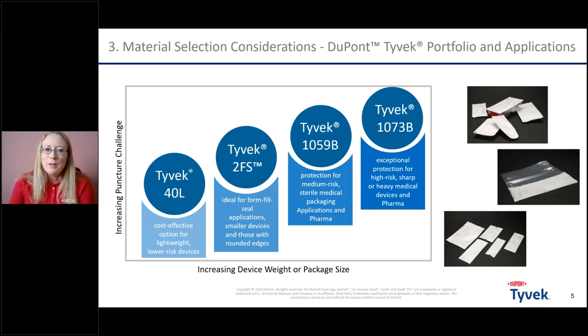On the right side, you can see some pictures of the packaging configurations I've just mentioned. You have rigid trays, for example, or form-fill-seal packaging, so thermoform trays with some lidding material, which can be Tyvek or medical grade paper. Then in the middle, you have a so-called header bag, which is three-quarter film with a porous Tyvek window, which allows for gas sterilization.